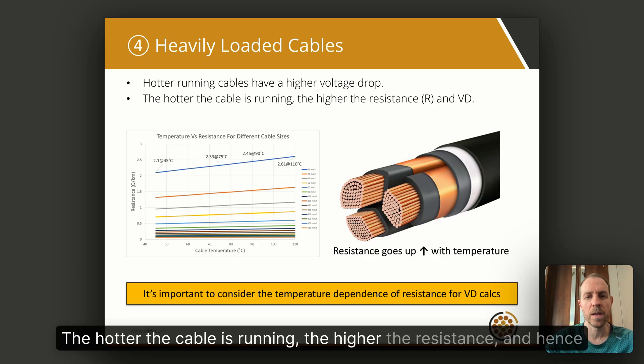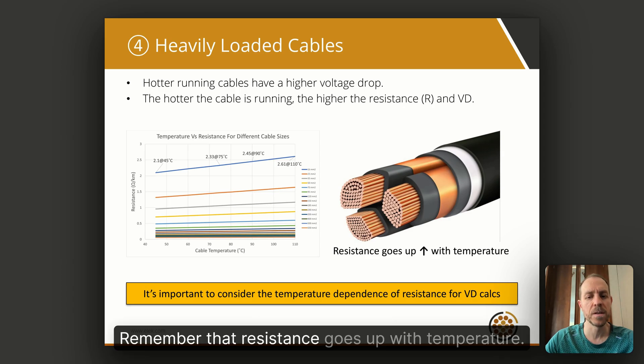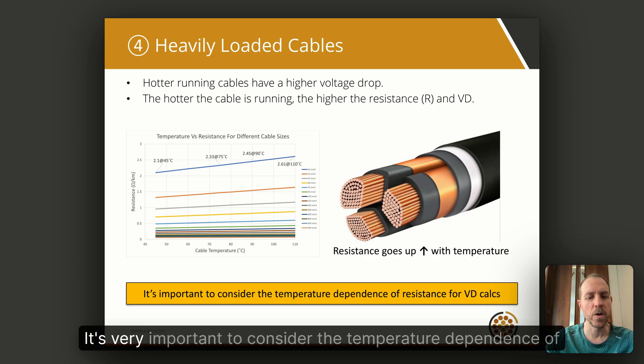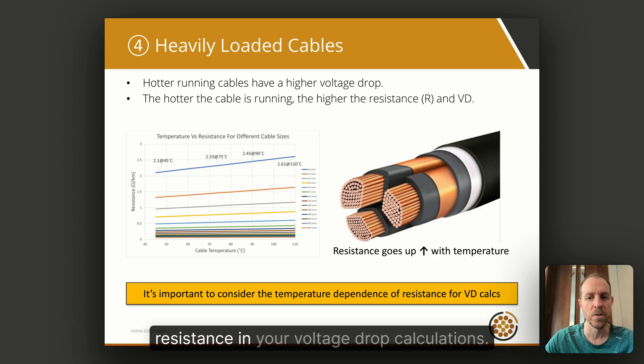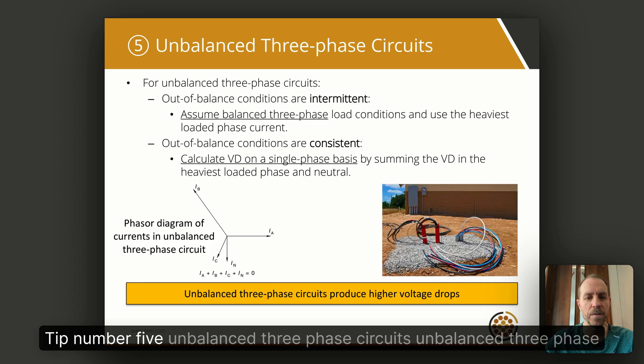Tip number four: heavily loaded cables. Hotter running cables have a higher voltage drop. The hotter the cable is running, the higher the resistance and hence the voltage drop. Remember that resistance goes up with temperature. It's very important to consider the temperature dependence of resistance in your voltage drop calculations.